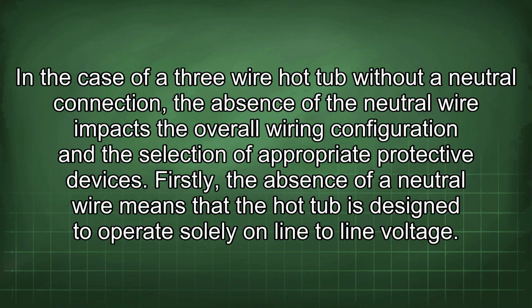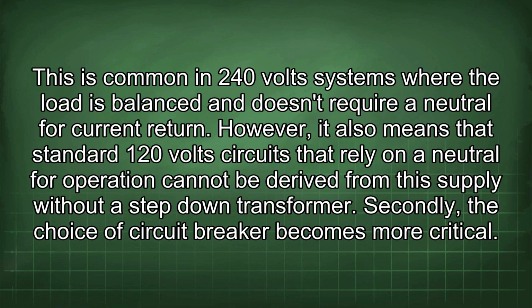In the case of a 3-wire hot tub without a neutral connection, the absence of the neutral wire impacts the overall wiring configuration and the selection of appropriate protective devices. Firstly, the absence of a neutral wire means that the hot tub is designed to operate solely on line-to-line voltage. This is common in 240-volt systems where the load is balanced and doesn't require a neutral for current return. However, it also means that standard 120-volt circuits that rely on a neutral for operation cannot be derived from this supply without a step-down transformer.